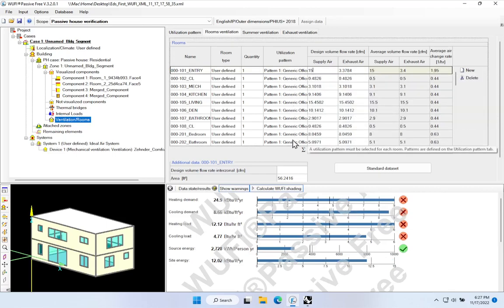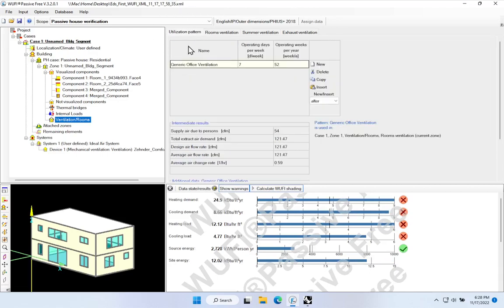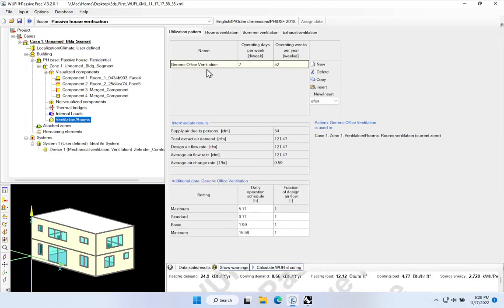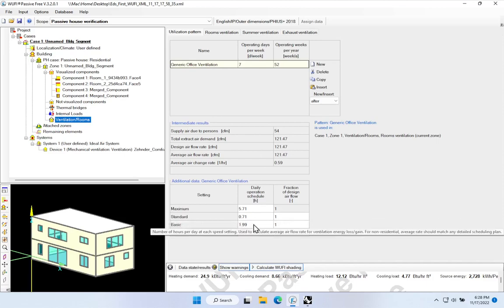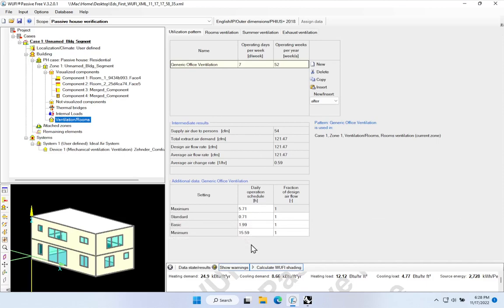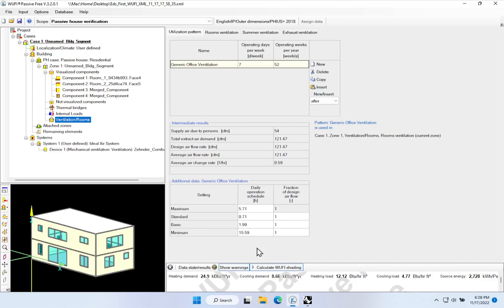The schedule gets defined over here in the utilization pattern worksheet. Here, we're able to build out whatever number of schedules we want. Notice we have one coming in called Generic Office Schedule. In this lower portion, we're able to enter a four-part breakdown of the ventilation air flows: a fraction of design air flow, and then a daily operation schedule in hours. This is a schedule of operation — at what speed is the fresh air ventilation going to be provided, and for how many hours per day will it be supplied at that rate?